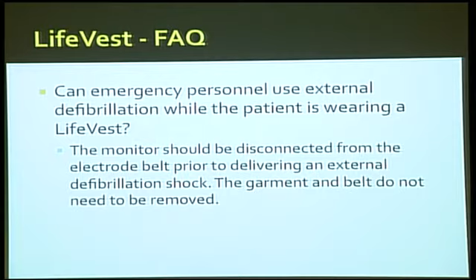Can you use an external defibrillator while the patient's wearing a LifeVest? If the thing isn't functioning correctly, yes. Disconnect the monitor from the electrode belt. What if the patient feels a vibration along with the alerts and voice prompts? That's part of the LifeVest trying to figure out if the patient's conscious. So they can press and hold the buttons to avoid a shock.